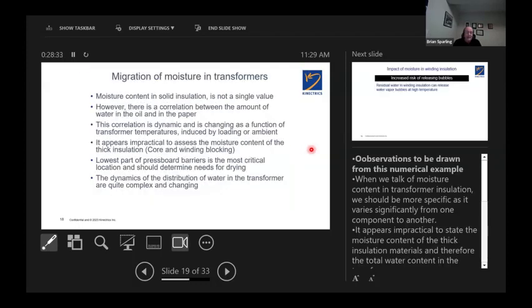So now, to complicate our dilemma, moisture content in the solid insulation is not a single value. There is a correlation between the amount of water in the oil and the paper, and this correlation is dynamic, as I was saying. Dynamic means it keeps moving back and forth as a function of temperature, induced by loading or by the ambient. We ignore totally the thick insulation around the core and the winding blocks. The interest is the lowest part at the winding, the barriers at the bottom of the winding, and the dynamics of distribution of the water is quite complex and changing.